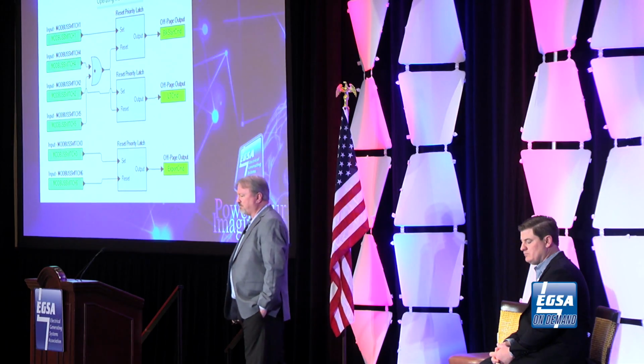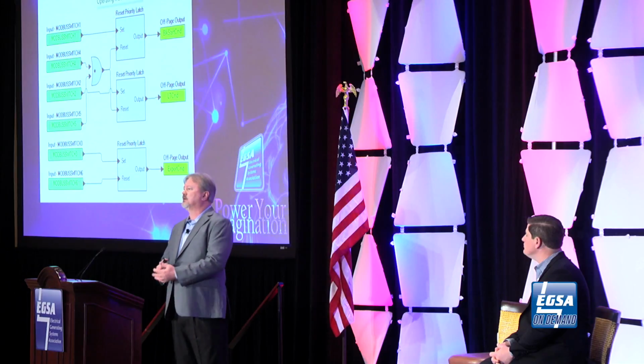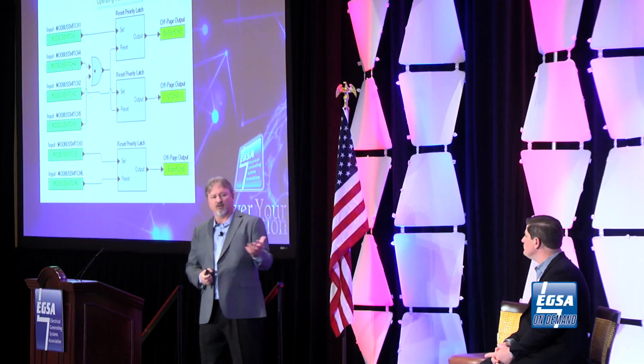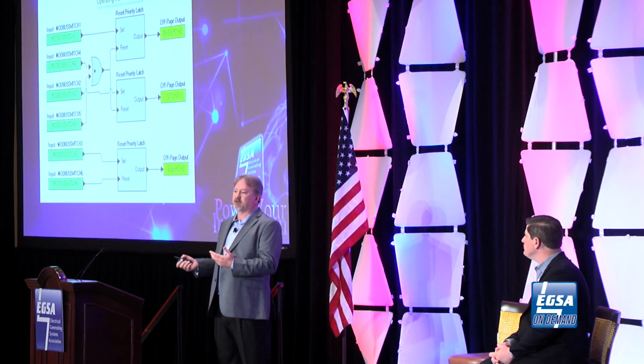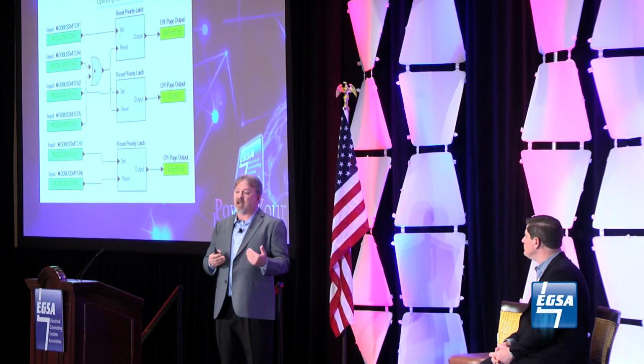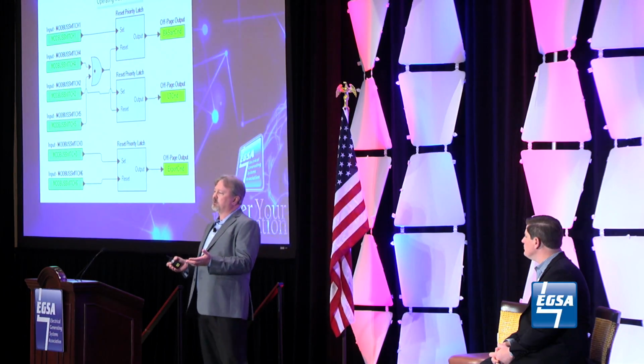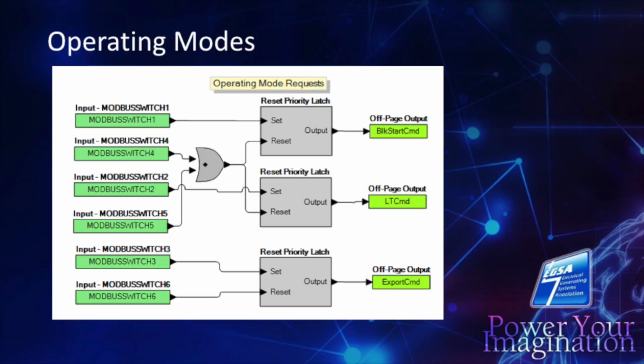We also have load takeover, and this is probably one of the bigger uses of the generators. Either locally or remotely, they can start the generators, bring them online, and take the plant offline. So it's a peak shave, but not a true peak shave, because we actually disconnect from the utility and run the plant offline. And then they can control that from Kansas City or locally, and along with the peak shaving, obviously we're capturing that 4CP avoidance, which is pretty big.